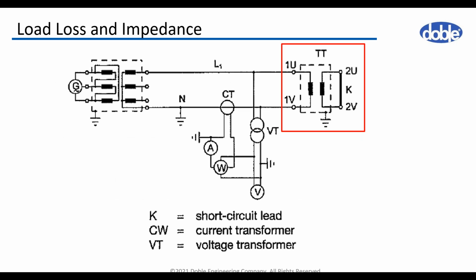This is a simplified diagram representing load loss and impedance measurement on a single phase transformer for simplicity. We have the test object in the red square with the low voltage winding shorted and high voltage applied from the test source. The measurement of voltage and current is performed via measuring transformers and a power analyzer. The power analyzer combines voltmeter, ammeter, and wattmeter in just one instrument. All modern laboratories use power analyzers instead of single meters. The source is represented by a generator and a suitable test transformer.